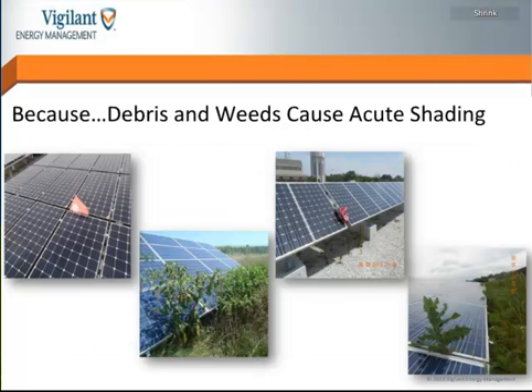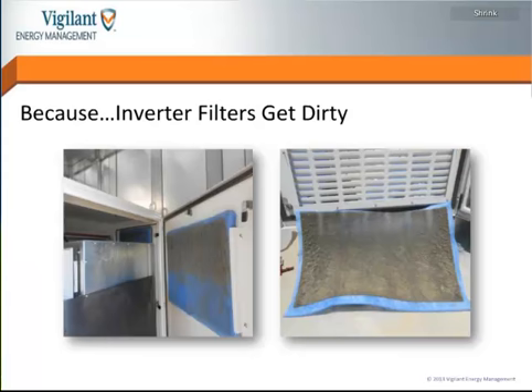Well, first off, oops, I'm advancing twice at a time here. Because inverter filters can get dirty. I'm going to go through like 5 or 6 slides of examples of what goes wrong pretty typically out in the field that gives justification for having a strong O&M program. And one of the most common things is just to have inverter filters get clogged up and dirty. This is very true for the desert Southwest in California, where there's a lot of dust, but these pictures were taken here in the east, and so we even have problems with dust and clogged filters here in the east. And of course, when the filters get clogged, that means that the cooling fans get overloaded, and they could prematurely fail, which would cause the inverter to fail. And then you're non-functioning and losing a lot of money just because some dirt found its way to your filters and they weren't cleaned out or replaced.